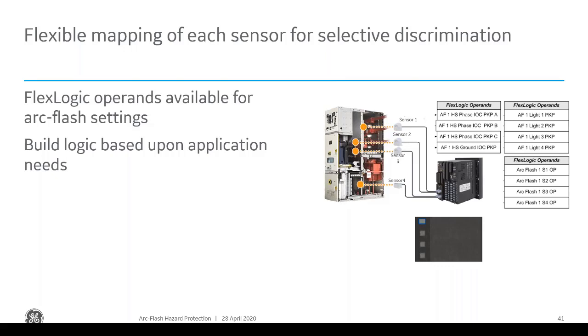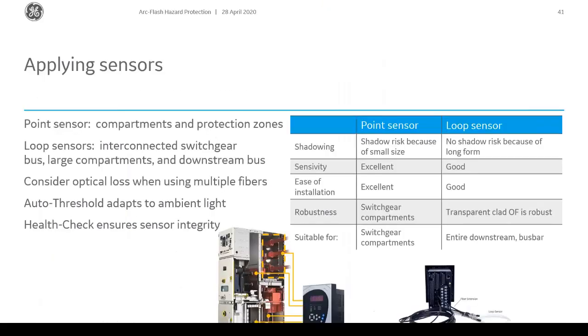When the sensor operates, it takes light and current to operate the output of the arc flash. However, if you need to build your own logic around this, we also provide the light and the IOC as separate items. So depending on the application, you can create your own logic because you have all of those points available.